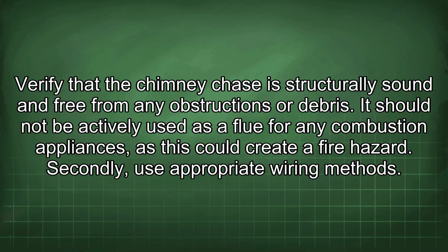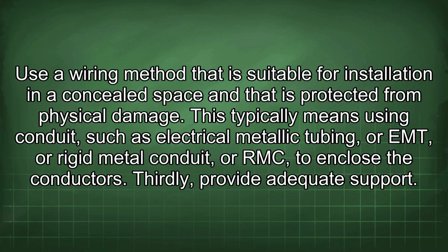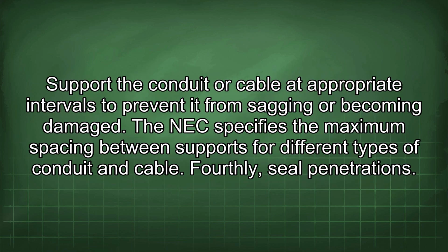Secondly, use appropriate wiring methods. Use a wiring method that is suitable for installation in a concealed space and that is protected from physical damage. This typically means using conduit, such as electrical metallic tubing or EMT, or rigid metal conduit, or RMC, to enclose the conductors. Thirdly, provide adequate support. Support the conduit or cable at appropriate intervals to prevent it from sagging or becoming damaged. The NEC specifies the maximum spacing between supports for different types of conduit and cable.